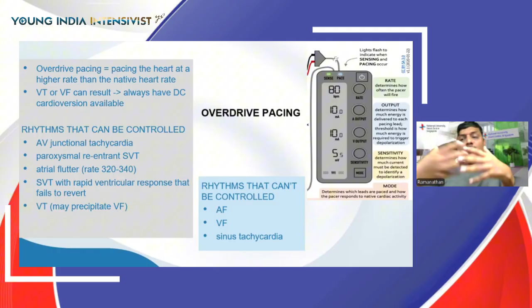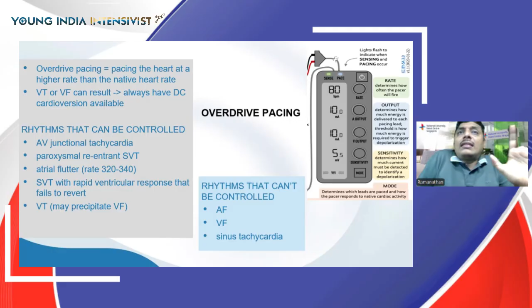So let us say your patient has an atrial flutter that's going at 140 or 150. You may want to pace the patient's atrium at a higher rate, say 220, to see if that can control the rhythm within the atrium to bring it back to normal. So rhythms that can be controlled with overdrive pacing are the junctional tachycardias, the reentrant SVTs, flutters, SVT with RVR. We usually don't try that with VT because it will precipitate VF. And AF, VF, and sinus tachycardia cannot be controlled with overdrive pacing. Again, another important use of the pacemaker in the general ICU.